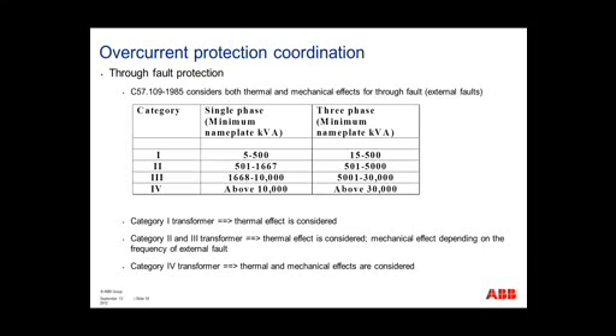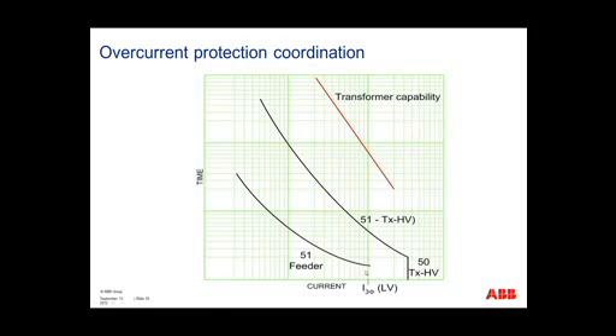Overcurrent protection and coordination. The importance of this, as a backup protection, is that it is not protecting for faults inside the transformer, but for faults external to the transformer that the transformer does see. Every time there is a close-in fault, the transformer is affected both through the thermal effect and the mechanical effect. Mechanical parts start to break down, and that needs to be considered when setting your overcurrent protection relays. The transformer comes with a capability curve, and if you exceed that transformer capability curve, you can guarantee damage to the transformer. So here we're trying to show the coordination between your time overcurrent and your instantaneous relays with relation to that transformer capability curve.